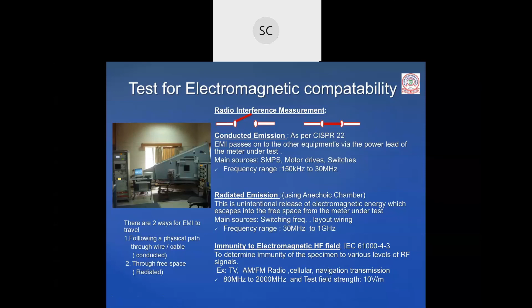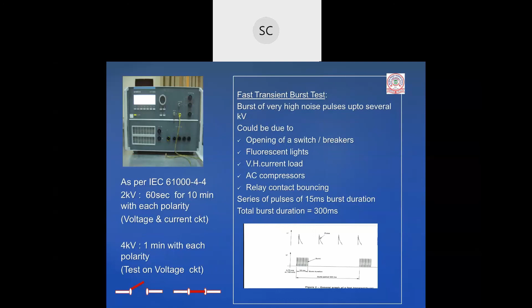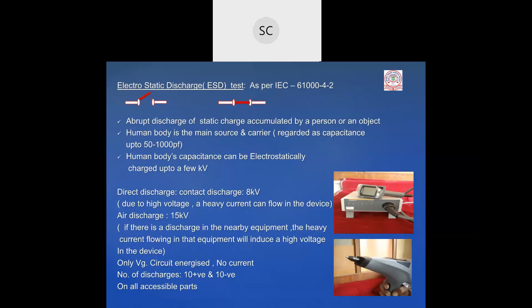Next is conducted immunity. In conducted immunity, there are different tests. One of them is fast transient burst. Probably all of you might have read in textbooks or somewhere else. Impulse is also one of the EMC tests. So fast transient burst is one thing. Second one is ESD. What is ESD? Especially in winter, when we are getting up from the chair, we get a shock. How do you get a shock from an insulated material? Because it is electric discharge. The accumulated charge gets discharged. Similarly, when we are touching polycarbonate meters and other meters, if our body is already charged, that discharge should not affect the operation or components used inside the meter. That is the intention. And voltage levels, test duration and how many cycles, all are as per the standards.